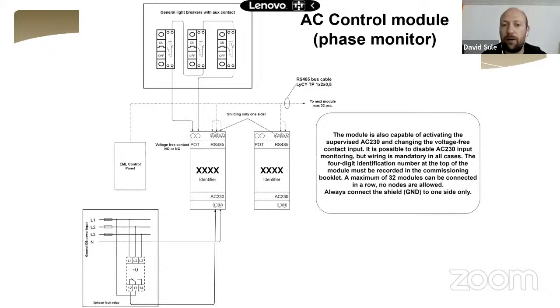But sometimes we just have to monitor the AC230 part of the module, and sometimes only the normally open or normally closed contact. For example, we have to get a signal from the fire alarm panel. So when the general fire alarm signal happens in the building, we can place one AC control device near the fire alarm output device, with just a simple normally closed contact for this device, and we can program it to control all of the luminaires in the building that need to be turned on when the fire alarm happens. And in this case, we don't have to monitor the AC230 input of this module. We can disable this function, but every time we have to connect it to AC230 from somewhere, because the AC control unit has a battery inside and we have to charge it.